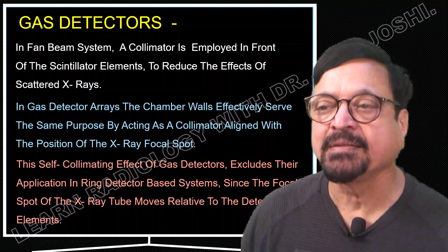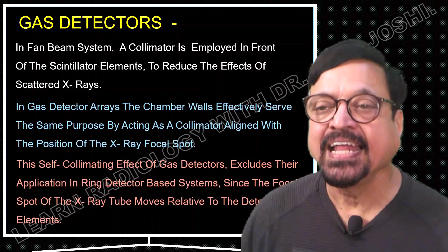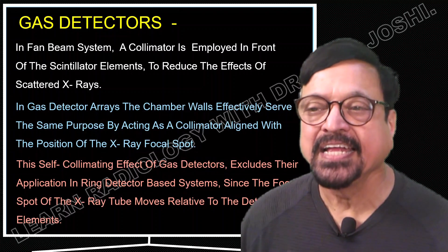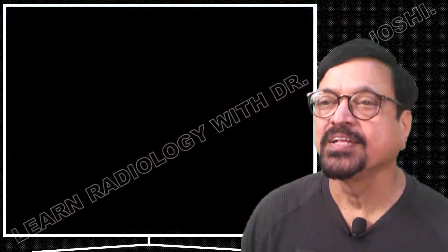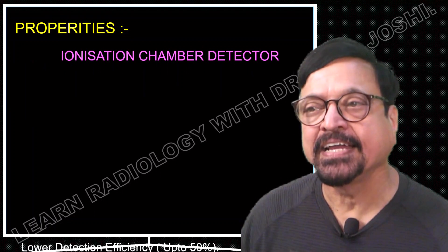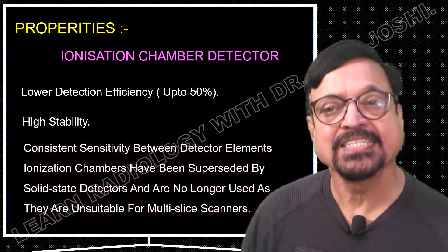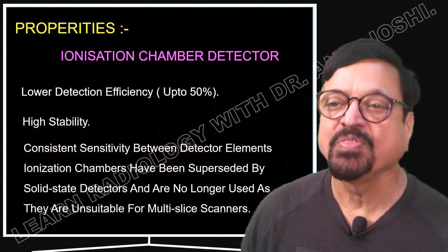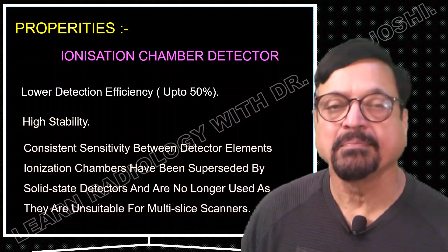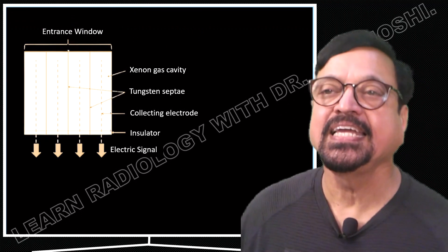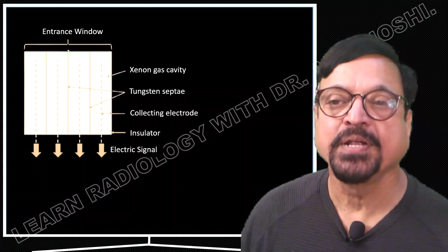The self-collimating effect excludes gas detectors from ring detector-based systems, since in those systems the focal spot of the X-ray tube moves relative to the detector element. These detectors are no longer used today — they were used in the past. Their properties included lower detection efficiency, maximum up to 50%, but they were highly stable with consistent sensitivity between detector elements. Ionization chambers have been superseded by solid-state detectors and are no longer used as they are unsuitable for multi-slice scanners. You can see the entrance window and exiting signals, and due to their septation they also act as collimators.